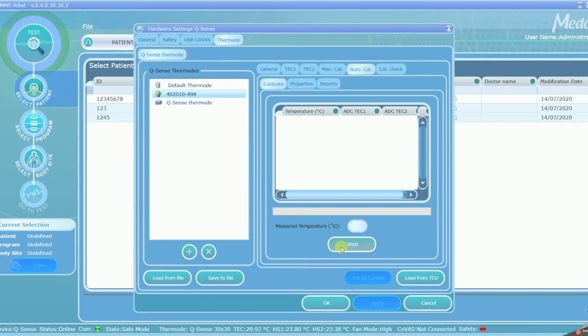And this is the most common procedure that you'll do with your calibration kit. The auto calibration is something that you just turn on and walk away from. During the auto calibration, the thermode will be checked on several points along the whole temperature range. This is depending on your device. Each temperature point will be checked for about 2 minutes. So take into account that this whole procedure will take you between 30 minutes and an hour.